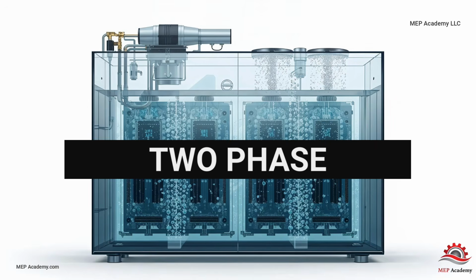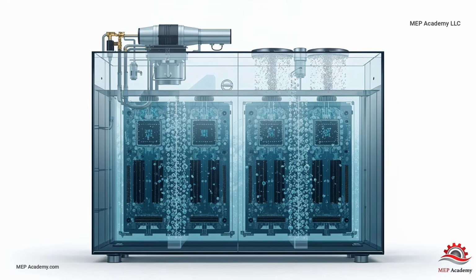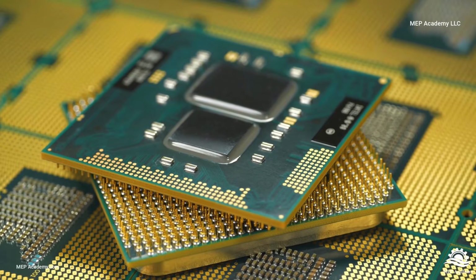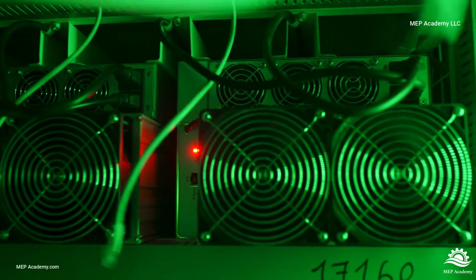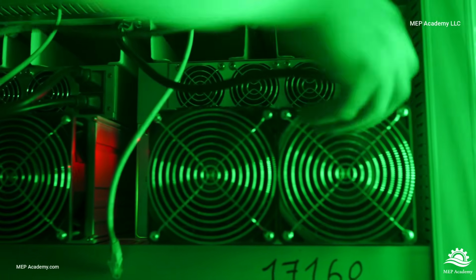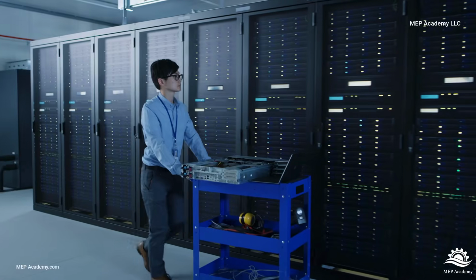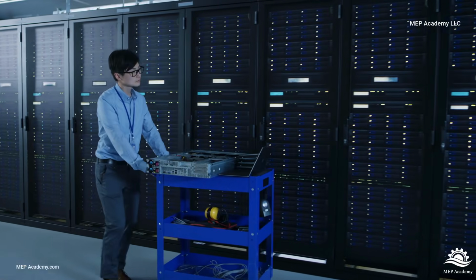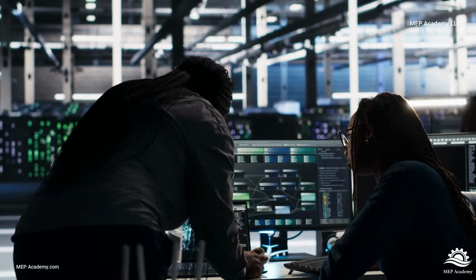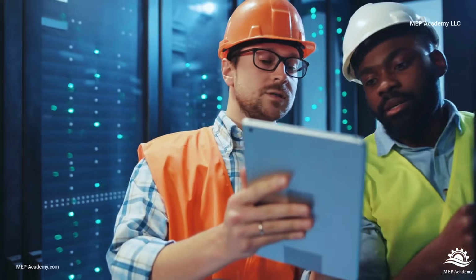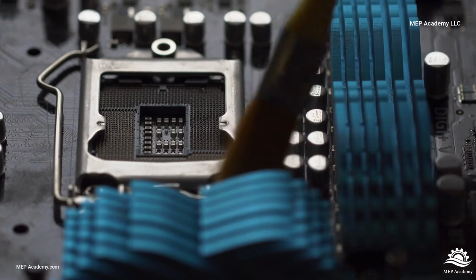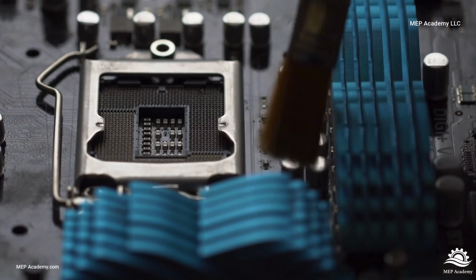In a two-phase system, the fluid actually boils when it contacts hot components. The vapor rises, condenses on a cooling surface, and returns as liquid. The process repeats continuously. Immersion cooling can support extremely high power densities while reducing the need for server fans and traditional airflow management. However, it introduces new challenges related to maintenance, equipment compatibility, operational procedures, and facility design. Because of these factors, immersion cooling remains less common than direct-to-chip cooling, although interest continues to grow.